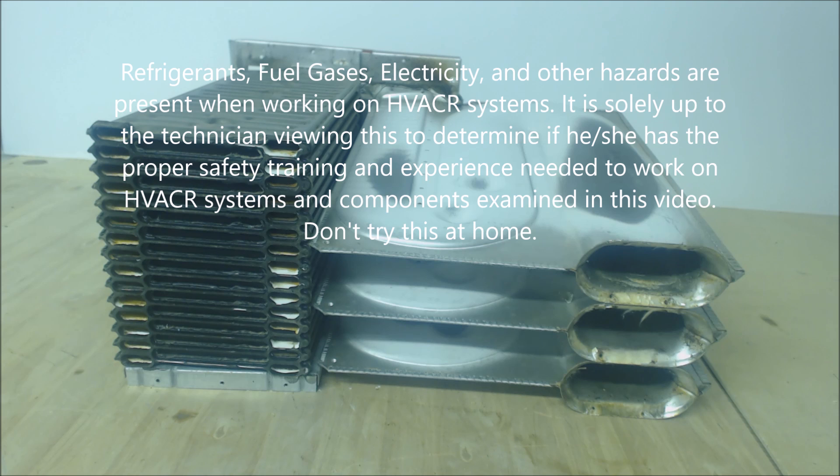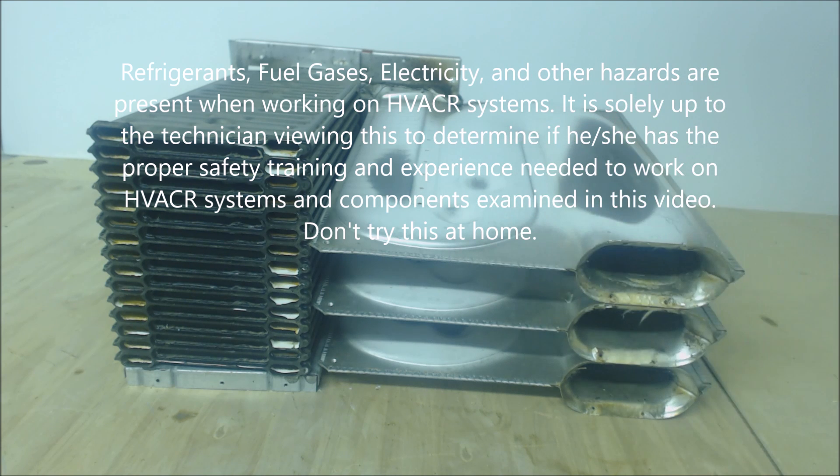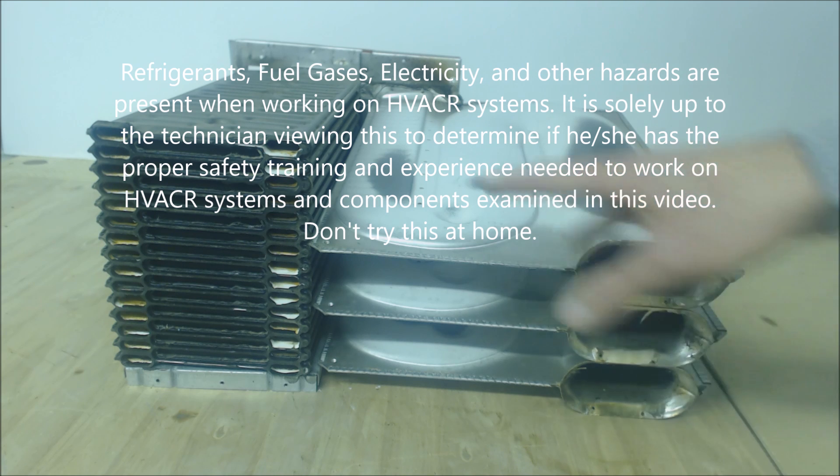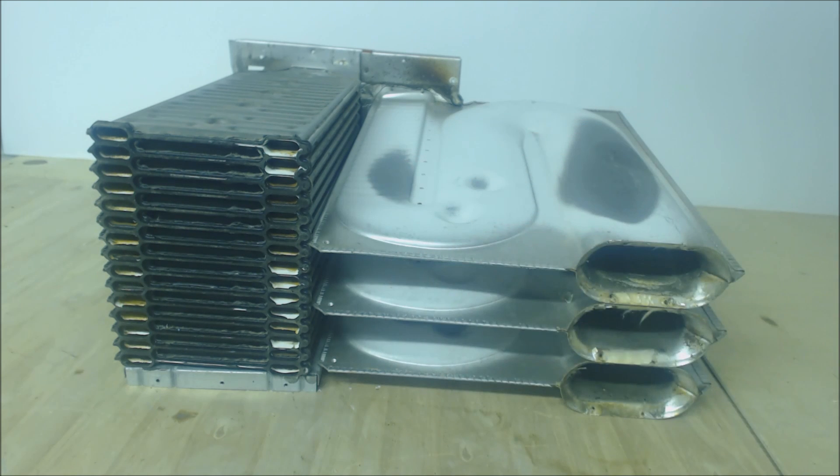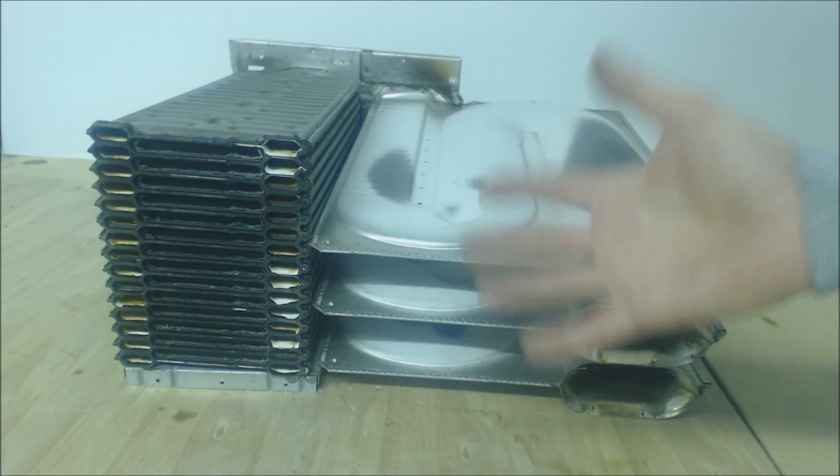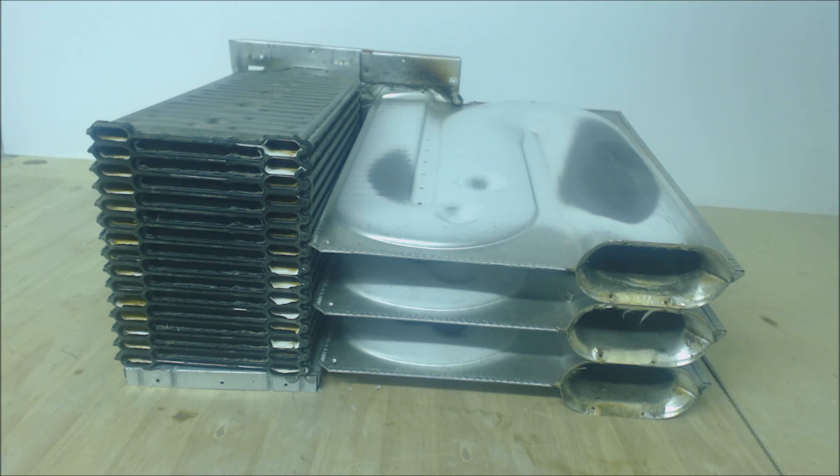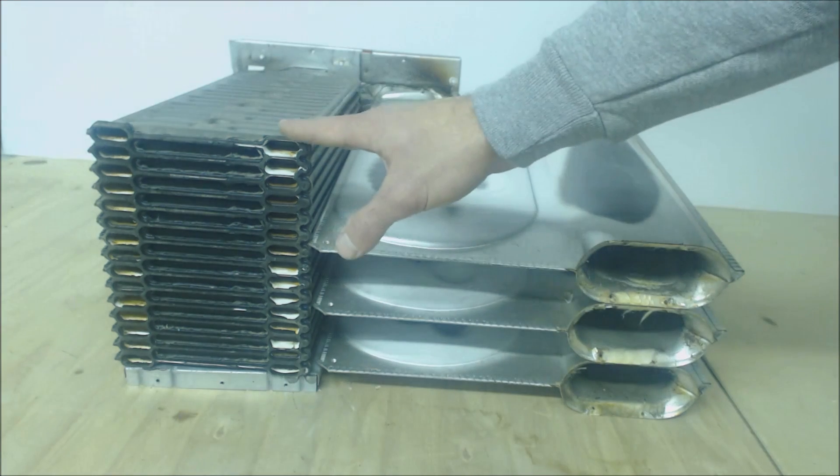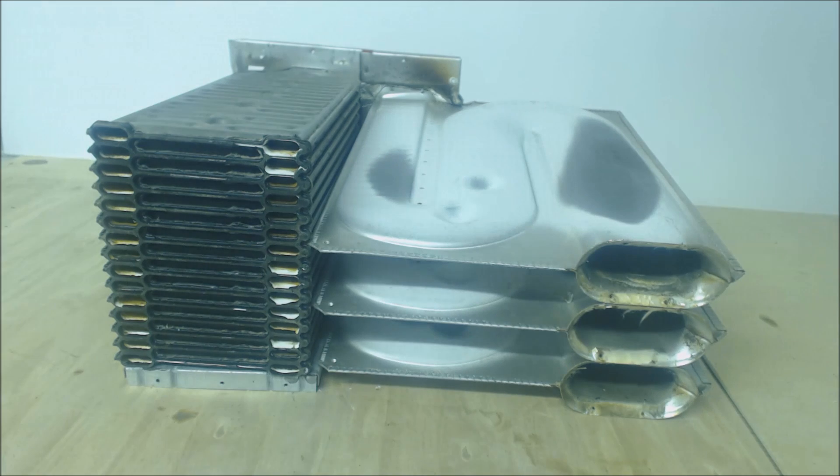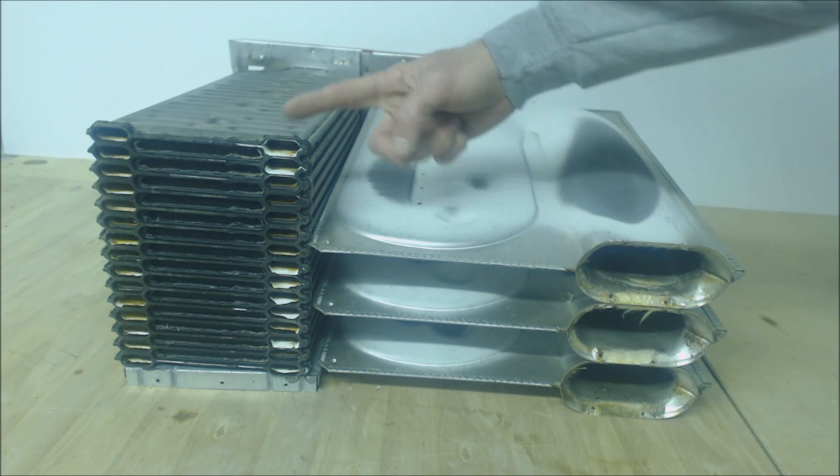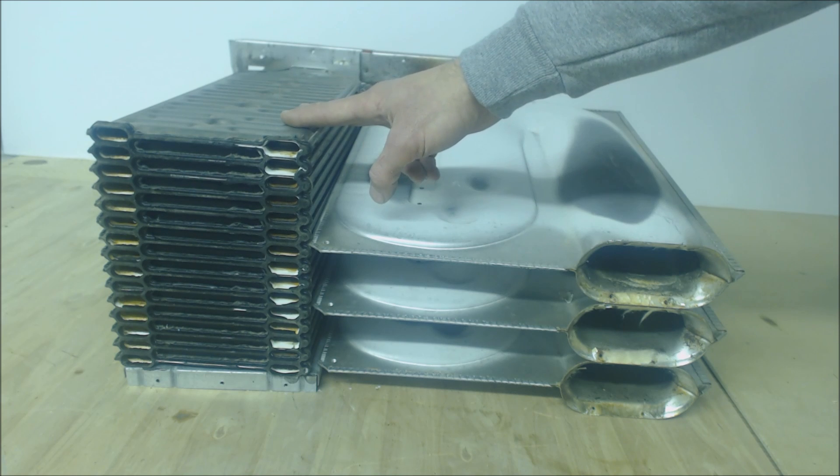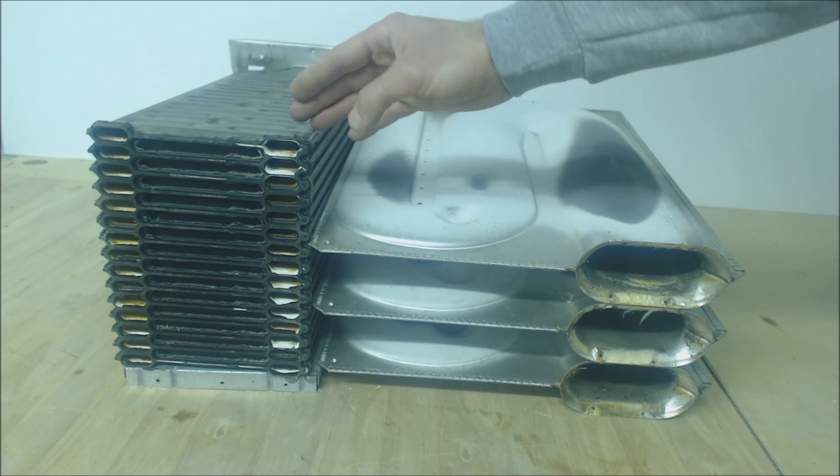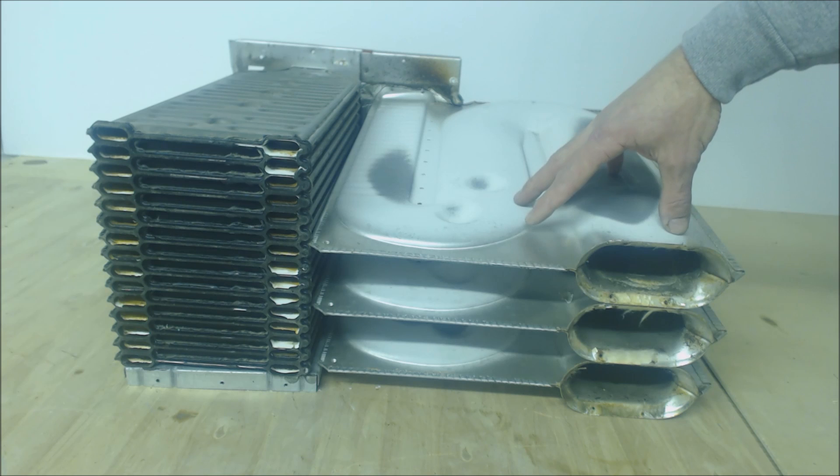Hey guys, this is the AC Service Tech. Today we're looking at heat exchanger failure. We're going to talk about a few items here. This is an older early 1990s 90% efficient furnace heat exchanger. These are the early heat exchangers that were used, and because of the way that the secondary heat exchanger was built, they tend to fail.